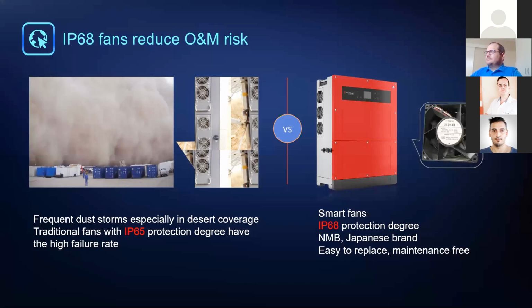We have IP68 fans incorporated into the inverter to account for any consideration, more specifically dust in desert conditions. That's usually a problem. And so these IP68 fans, they're manufactured by the brand NMB, which is a Japanese brand. They alleviate that fan issue that is generally considered an issue with inverters.